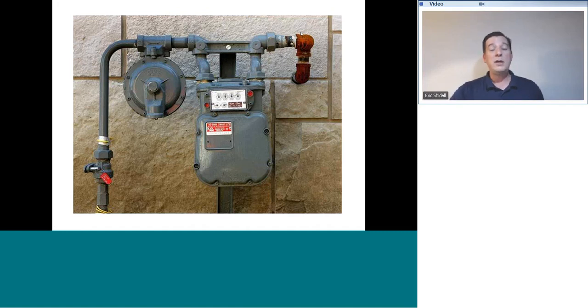But if you need to run a new gas line, say you're going to install a brand new tankless water heater, you will most likely need to run a new gas line for that. And the best way to do that is to install a T-fitting where that elbow is and run your brand new gas line from there on in. If your new gas requirement for that building is now greater than what the meter is able to provide, most utility providers will replace the meter for free with a larger model that will handle the new gas supply.